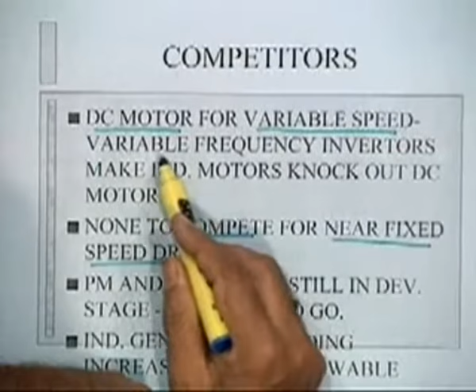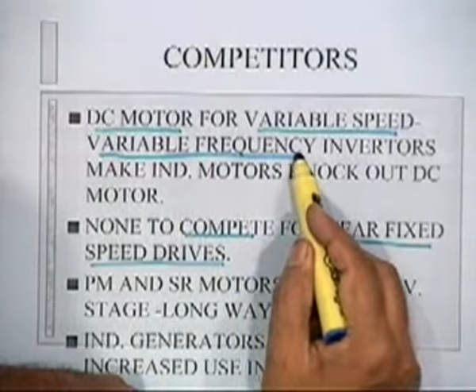That is the DC motor. Now, nowadays induction motors are also competing, because with the advent of power electronic switches, you can have variable frequency inverters. You can change the frequency. Earlier it was not easy to change the frequency. Therefore, with the advent of these variable frequency inverters, induction motors knock out the DC motor. So the DC motor industries are getting into applications which are slowly shrinking. So induction motors are competing very, very effectively on adjustable speed drives or variable speed drives.